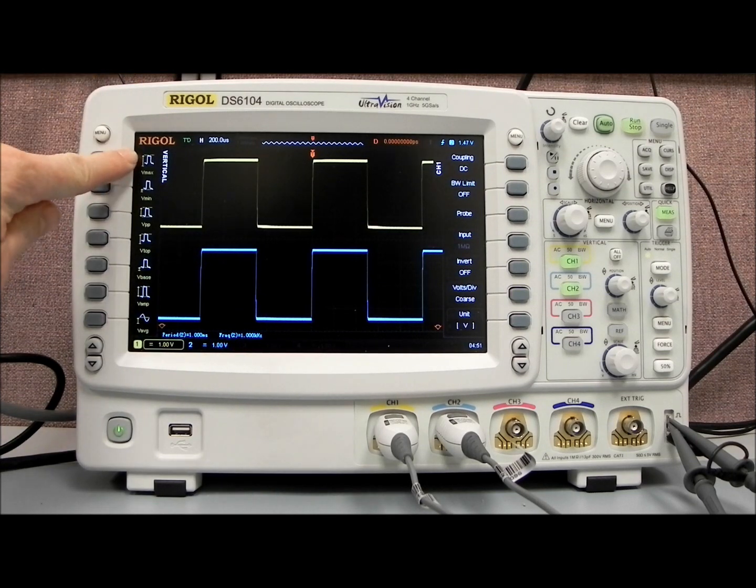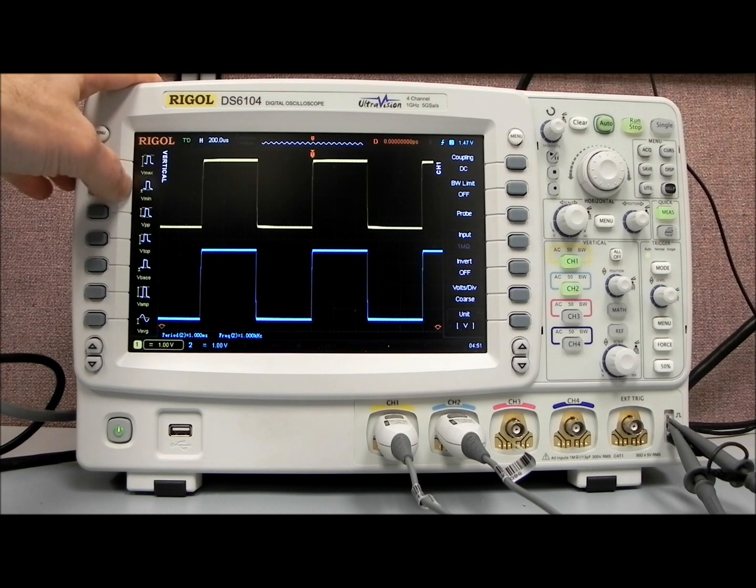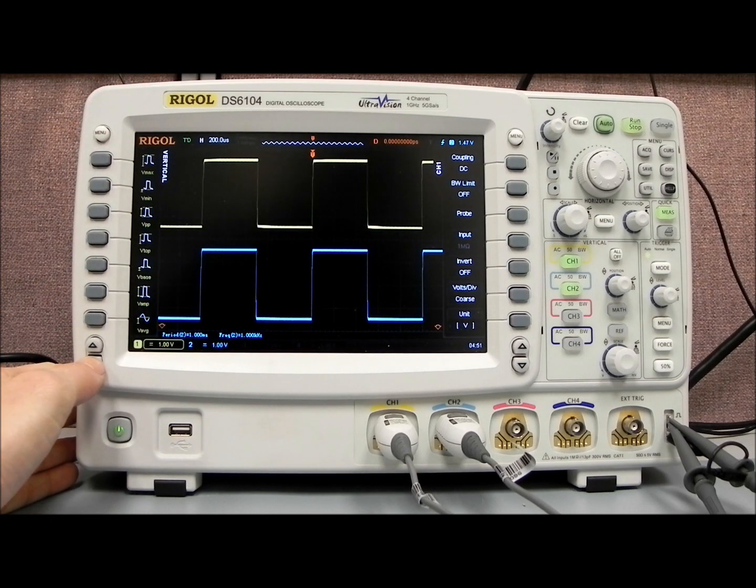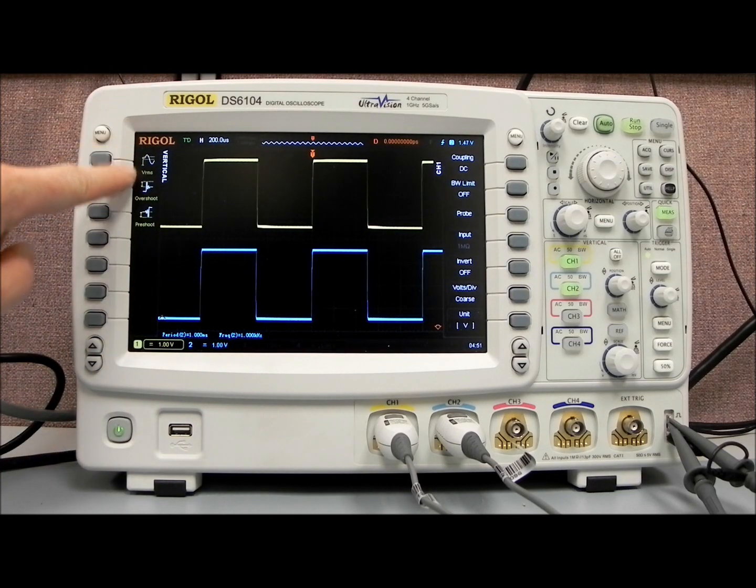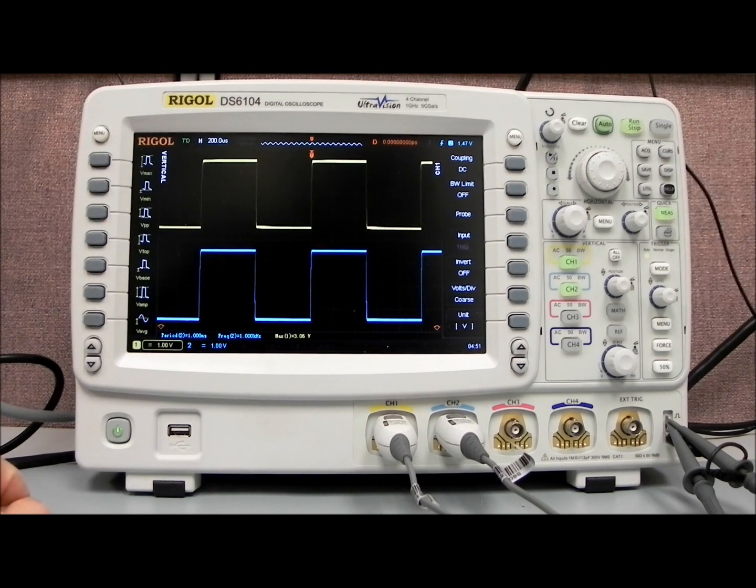What I'd really like to highlight is some of the quick measurements we have. If we press this menu key on the left-hand side, you'll see it says vertical currently. If we pull that out, now we have all of the vertical measurements that we have at our fingertips. We have max, min, peak-to-peak, top, v-base, v-amplitude, and v-average. If we down arrow, you can also see we have VRMS, overshoot, and preshoot.